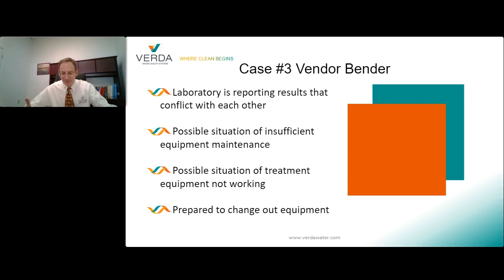I had a similar, but a different experience at another site where the local water test laboratory was showing a steady increase of water hardness in the utility water over the past several months, from a historical average of about 110 milligrams per liter. And it ranged from about 68 on the low side up to about 188, the worst of months. So over time, in recent months, that was increasing. That was going up. So the hardness readings were over 200, and then it actually spiked up to 350 milligrams per liter. So first of all, you're just way over the AAMI threshold of what's acceptable water to be using in your SPS.